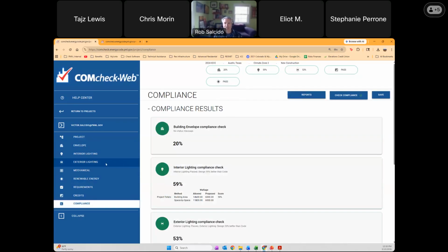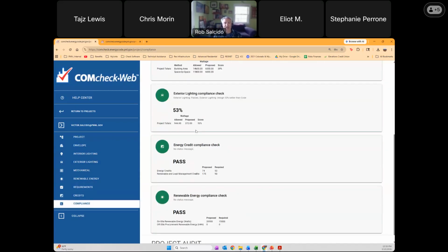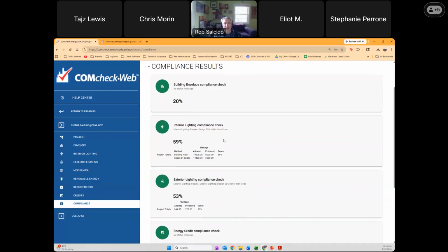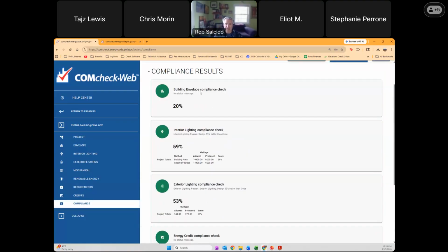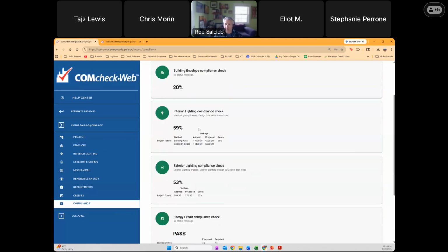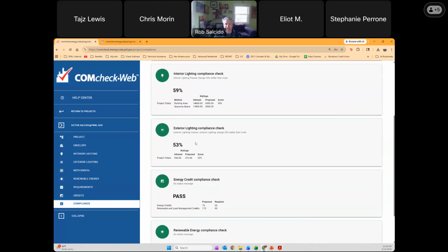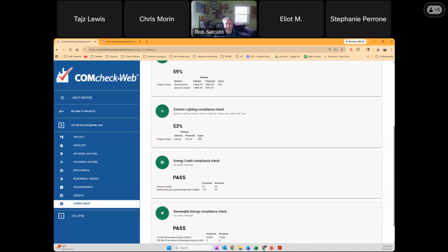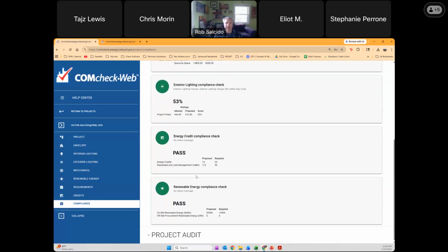Within the compliance screen, we've checked compliance and everything's passing. The envelope has either the UA compliance or the Appendix C simulation compliance. Interior lighting can use the building area method or the space by space method. Exterior lighting has its own compliance methodology for looking at allowed power. The mechanical side doesn't have a general compliance, since there's no method in the code that says mechanical complies overall. Each system has its own requirements, so there's no mechanical compliance banner here. It's checked within each system, each component, and verified in the report.